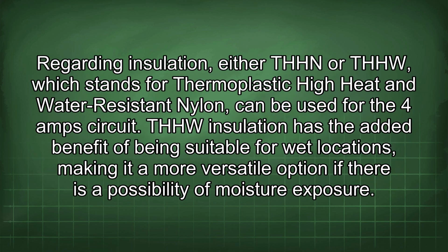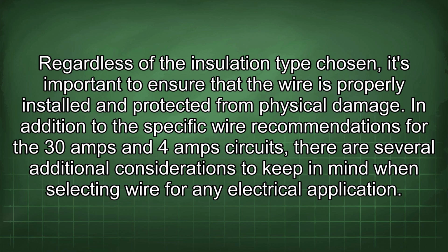Regarding insulation, either THHN or THHW, which stands for thermoplastic high heat and water resistant nylon, can be used for the 4 amp circuit. THHW insulation has the added benefit of being suitable for wet locations, making it a more versatile option if there is a possibility of moisture exposure.